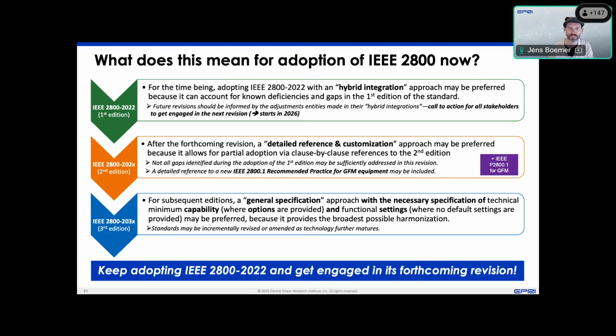Second, once the next revision is available, a detailed reference and customization approach can be used, because that would allow for more of a partial adoption and more consistency. But maybe not all gaps will have been addressed in that next revision. But the recommended practice for grid forming equipment may then be available and could also be referred to. And we do expect that after the next revision, there will be a subsequent revision. And hopefully in the third revision, we all have a standard that has closed gaps and is consistent. So maybe later on, entities can move towards a general specification, which is the most harmonized and coordinated way of adopting a standard like IEEE 2800. So keep adopting it and get engaged now.